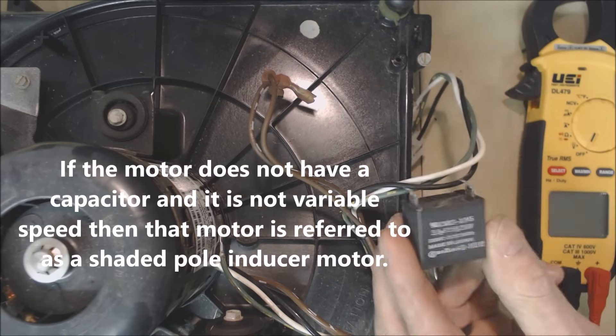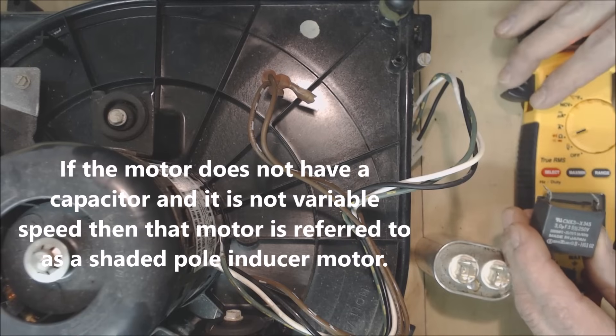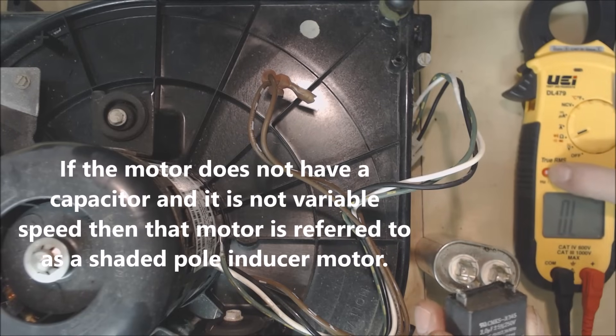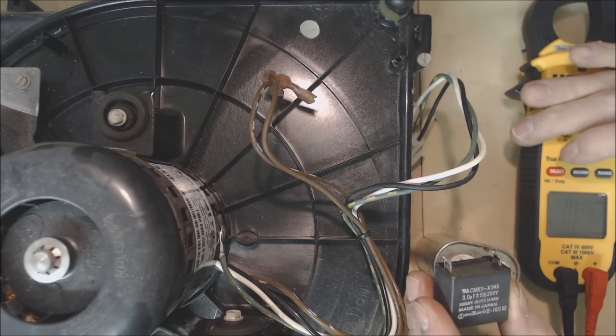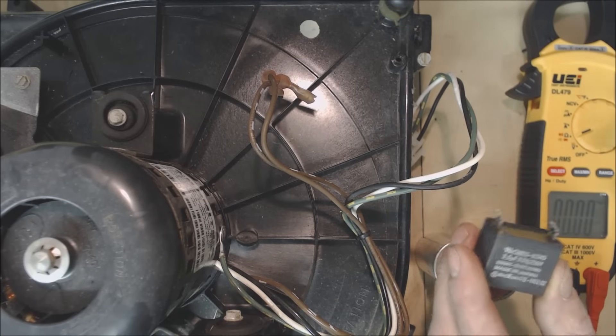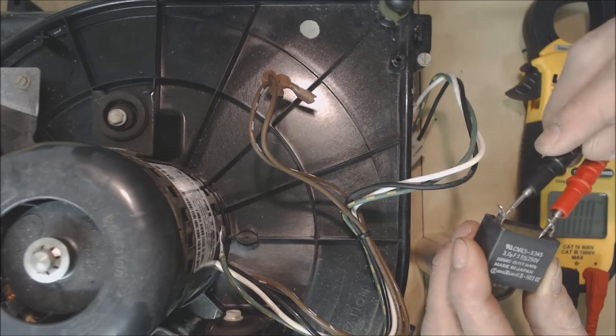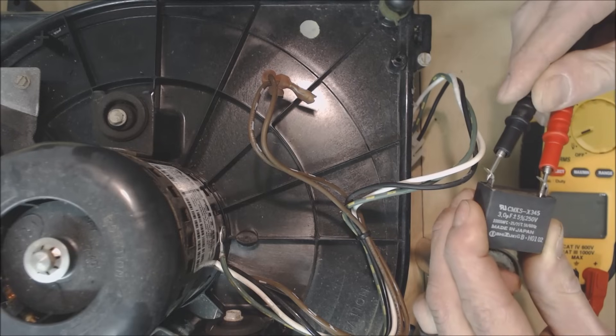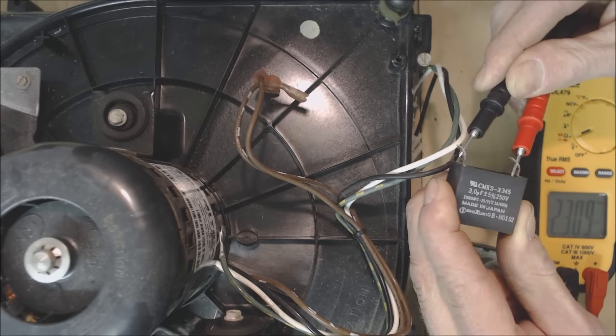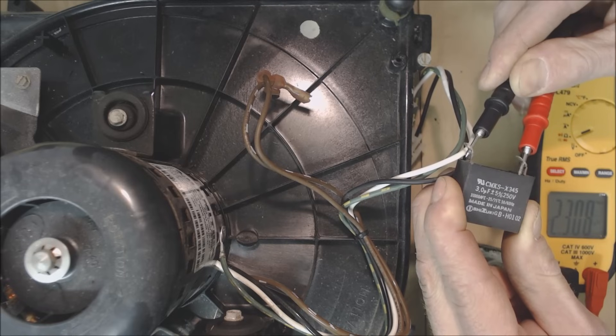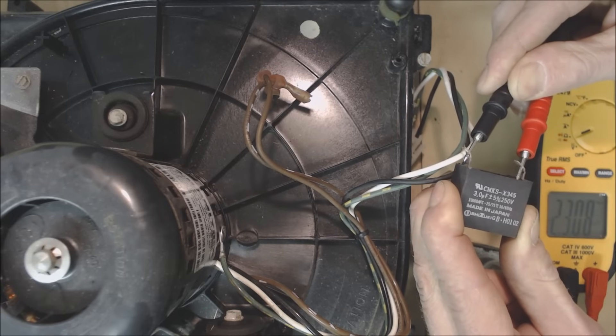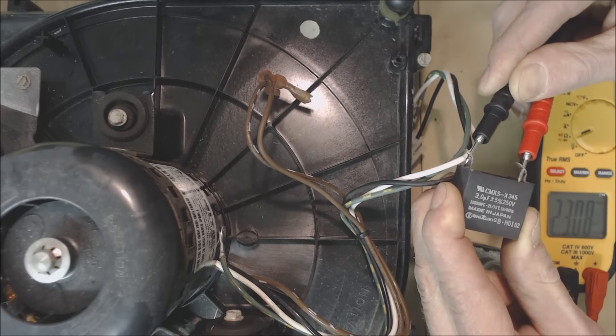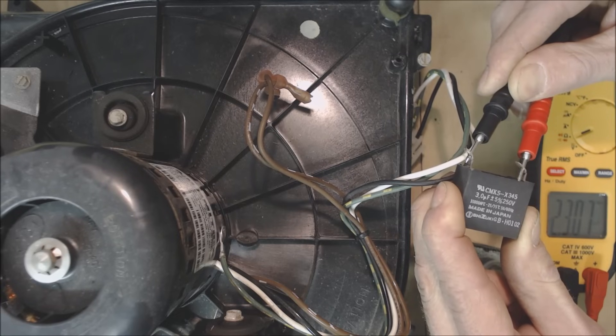So we're going to go ahead and test this with a multimeter. We're going to turn this on to microfarads. So we're going to have to hit this select button and then we're going to go ahead and check our microfarad reading. We're going to hold this in and you want to give it possibly up to even you know 15 seconds or so just in order to make sure that this is correct. So you see our reading right here is 2.3 UF.